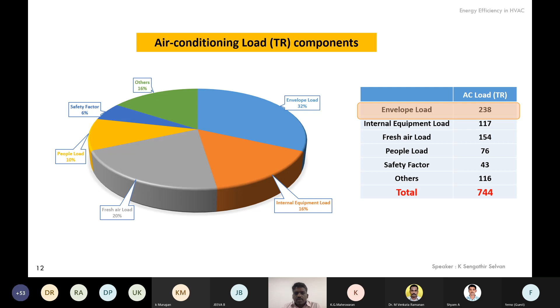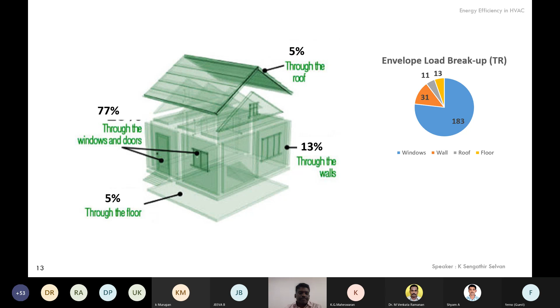Okay, so within this envelope load, what you can see, we have taken the base case building as 96%, where the window wall ratio was around 96%. You can see out of around 238 TR, 183 tons is actually required for windows only. So 77% is through windows, and through floor it is very little, and roof also is very little, mainly because we have underdeck insulation. And for through walls, since it's a brick wall, we have only 13%. So you can see that the majority comes from windows, and that gives the bigger opportunity.